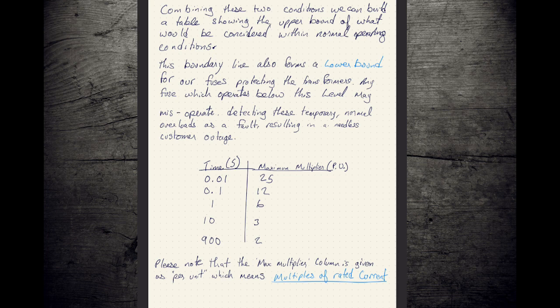And so in that hot load inrush period, when we're setting up those magnetic fields, we see 25 times per unit. Per unit is multiples of the rated current flow. So if you have a transformer and 100% of its rating is 10 amps, that means for the first hundredth of a second, you're not seeing 10 amps flow through that transformer, you're seeing 250. A tenth of a second after power is on, that 250 amps has dropped to 120, but you're still putting 120 amps through a transformer that's only designed for 10.